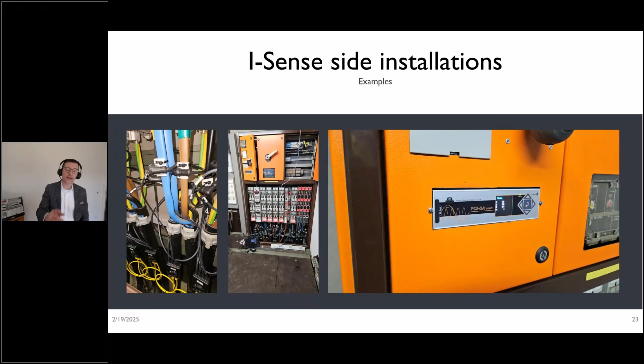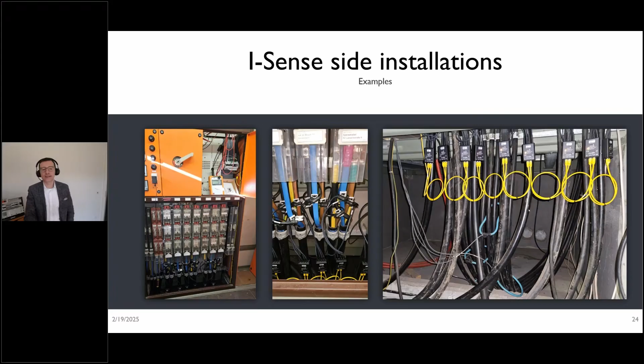This customer is using the PQI-LV, and you can see the iSense is directly installed at the cable, just plugged in a daisy chain to each other. The addressing is done automatically, you just have to install it and make one setting inside the device itself. Then the device will record the feeders to the system, and also has the opportunity to provide this data into different protocols like IEC 104 or MQTT as an example.